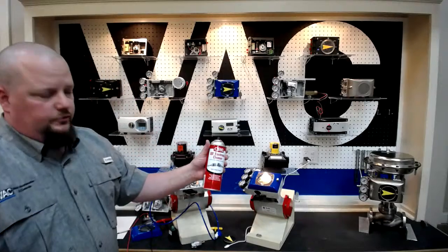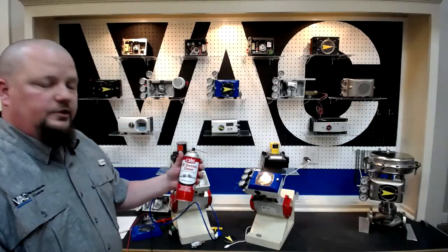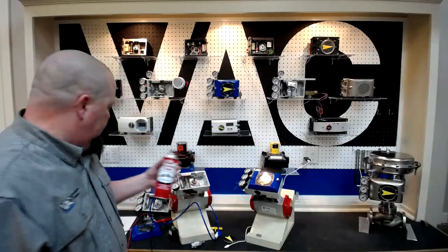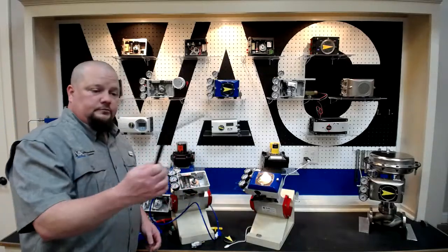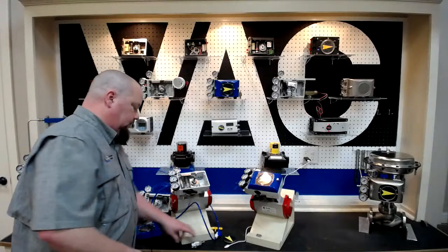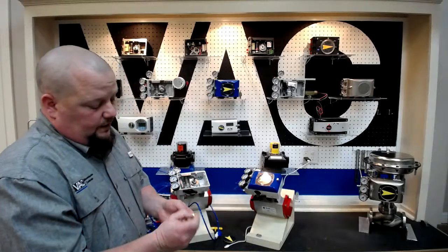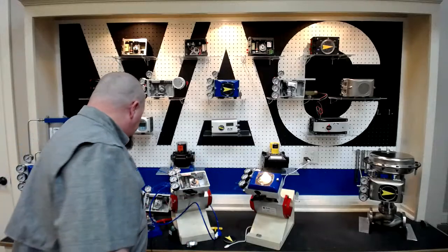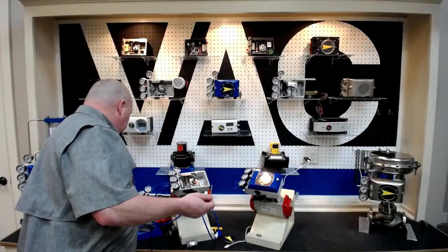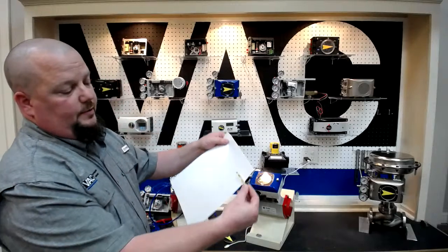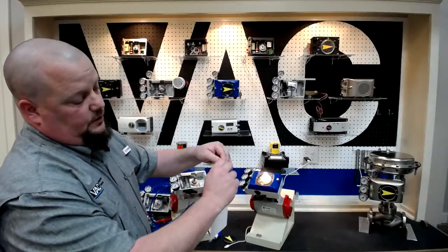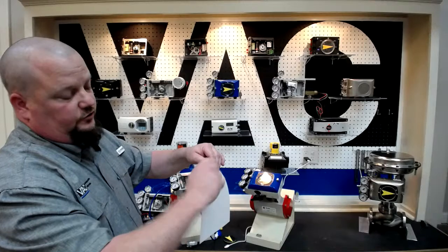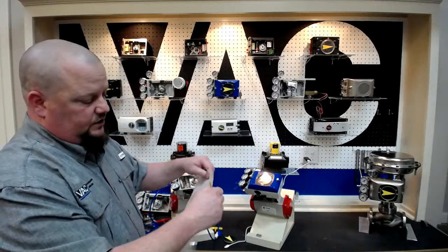We use CRC industrial cleaner. We want to use something with non-residue, and a pipe cleaner, a simple craft shop style pipe cleaner. What we'll do is pull the pilot out, the spool out, and spray through it. Then you can clean the pilot with just a piece of white paper. You'll pinch your fingers in there on the stem, and turn each one of those lobes and polish each lobe.